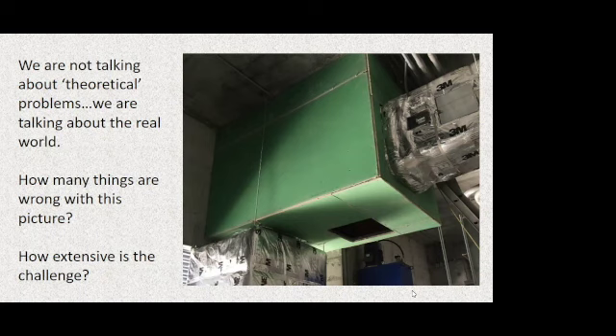Again, drywall on some lightweight framing is not fire rated. It needs to follow the designs for a compartment that can be supported in the air, and that means 3 layers of drywall minimally on the bottom, a shaft liner, and a heavy gauge, thick gauge, deep channel stud, CH stud on the bottom panel, 2 layers of drywall with a shaft liner on the sides, and those can use wall studs if they stay within the 48-inch maximum depth limit for those designs. If you can't stay inside those designs like they did for this box because the box is too long, then you need to do what? You need to do something different than drywall.